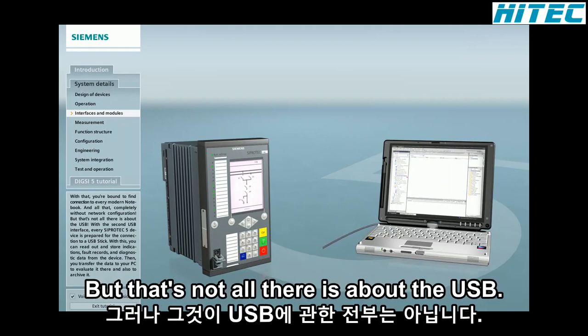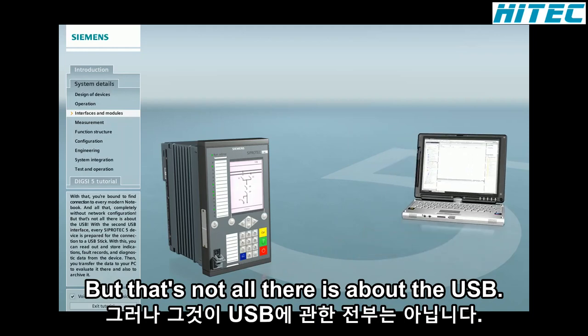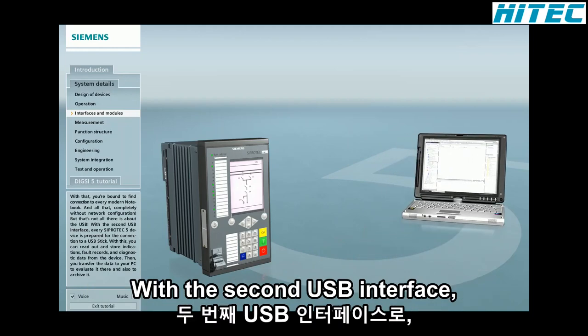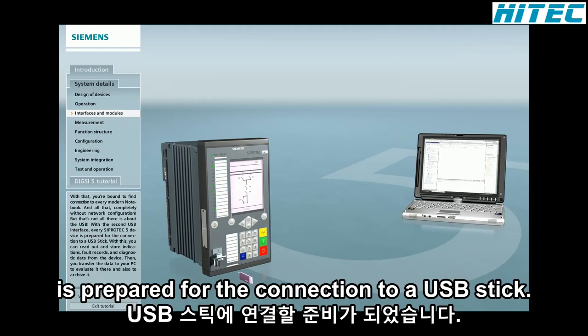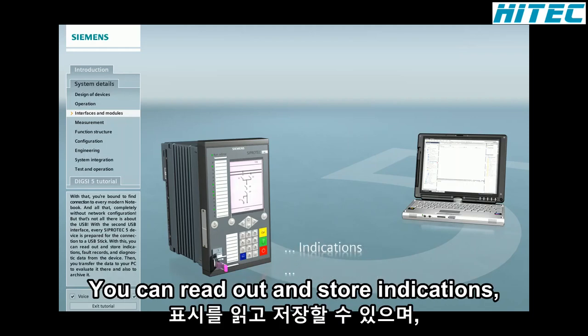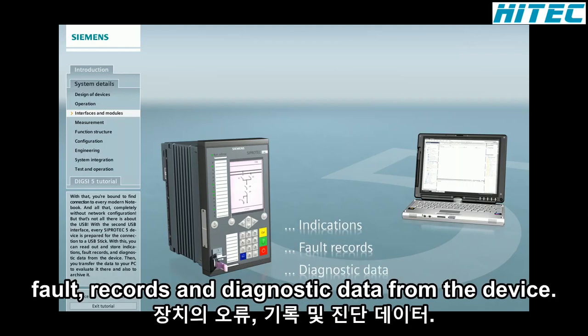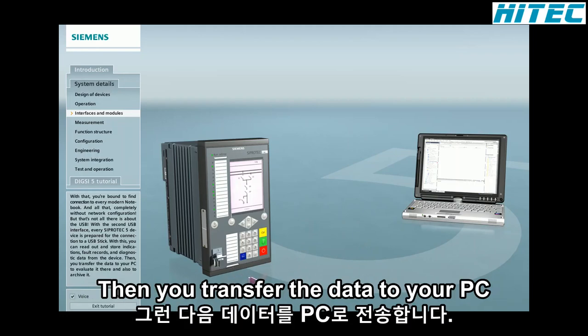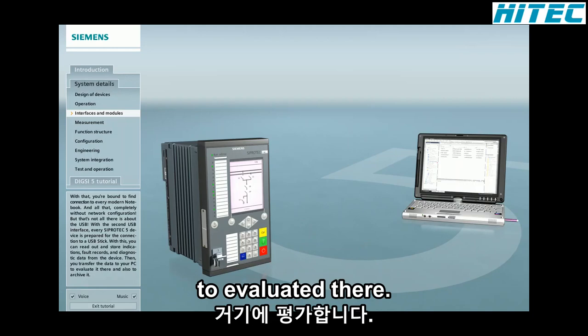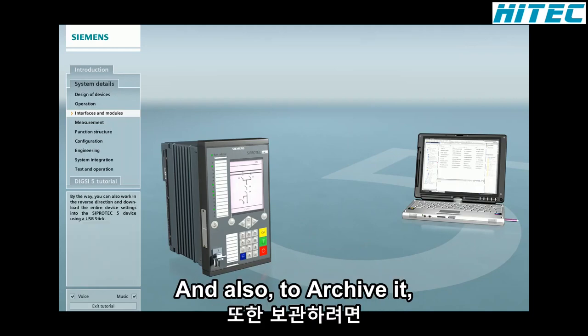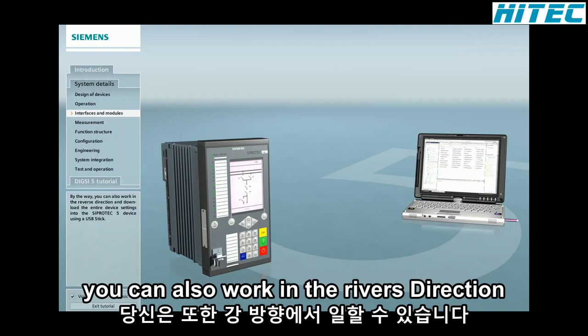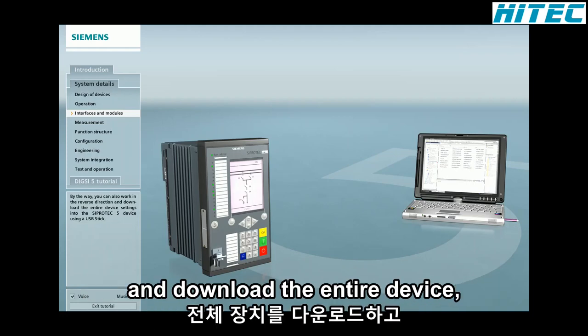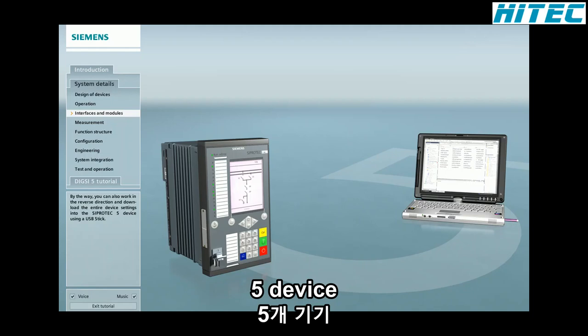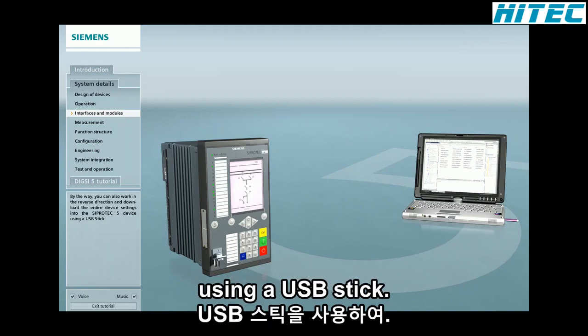But that's not all there is about the USB. With the second USB interface, every SIPROTEC 5 device is prepared for the connection to a USB stick. With this, you can read out and store indications, fault records, and diagnostic data from the device. Then you transfer the data to your PC to evaluate it there and also to archive it. By the way, you can also work in the reverse direction and download the entire device settings into the SIPROTEC 5 device using a USB stick.